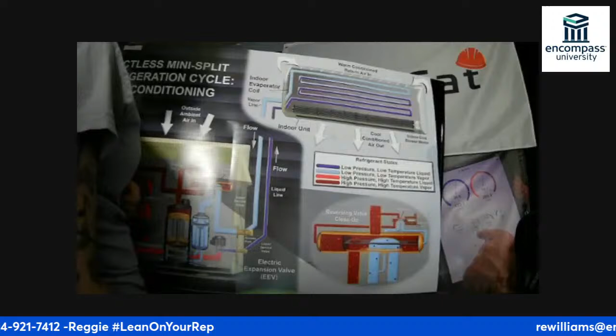When we put it in heat mode from cool mode, this reversing valve is going to slide. It stops the flow here and makes the flow go here instead. We have three choices here — we also have a discharge — but basically this slider will slide over and let it come down this way, or slide the other way and let it come down that way. That is the only component that chooses whether we are in heat or air conditioning.